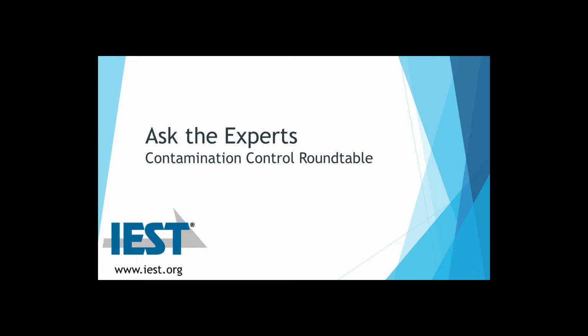Yes, ma'am. It's always subject to regulations. And if you're in a regulated industry, then that takes the first priority. If you're in a non-regulated industry, you are correct in saying that there are some exceptions when you do continuous monitoring. There are many semiconductor firms that do not do a formal certification. They simply do continuous monitoring with numerous amounts of locations. And for them, if they're not interested in following 14644-1, if they're not regulated, and if they certainly don't need 14644-1 as part of their ISO 9000 certification, then it would probably not be needed.